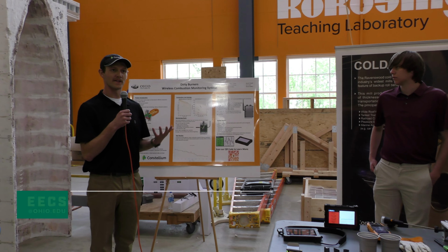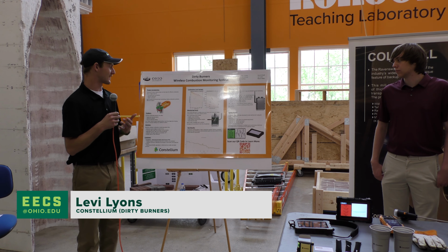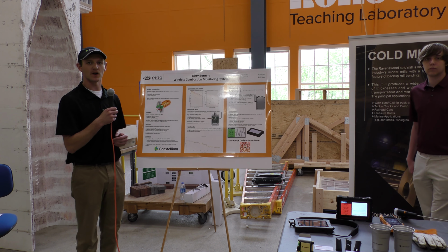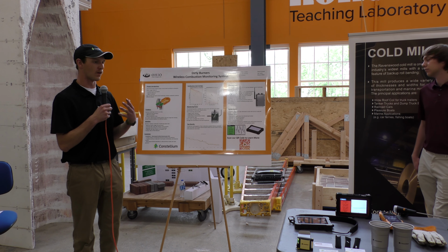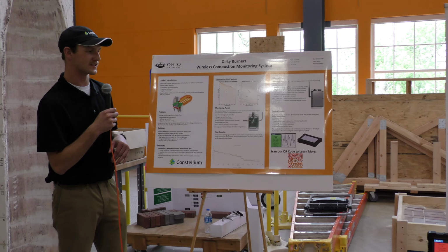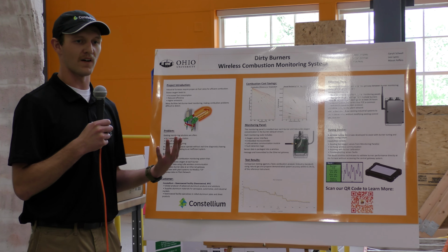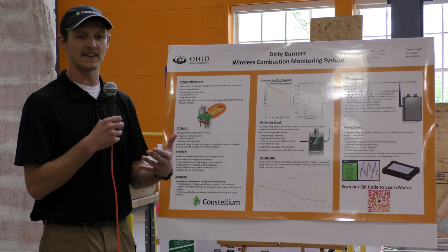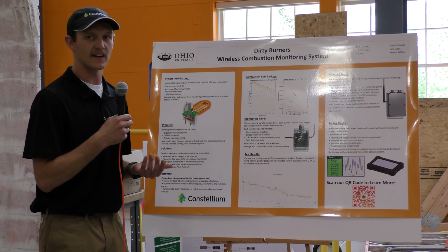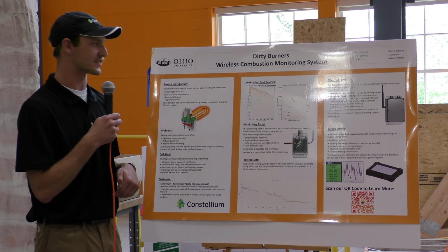So you may ask why you care about excess oxygen. Basically that's a main constituent in the combustion process, in any combustion process, in a car engine or a wood stove or propane or any natural gas combustion system. What you put in is air and fuel, and you get out CO2 and heat and a little bit of air that's left over. So what we're monitoring is excess air, because that's very determinant in the efficiency of the entire system.